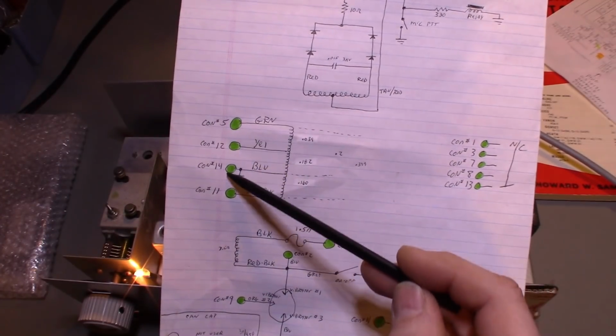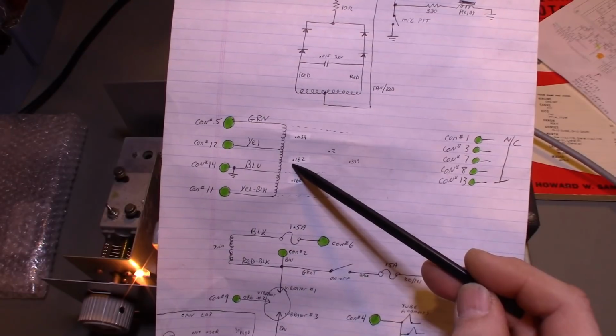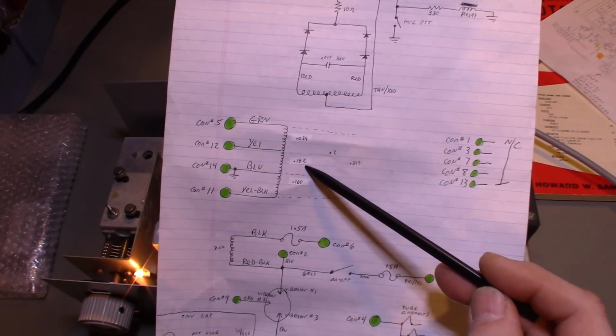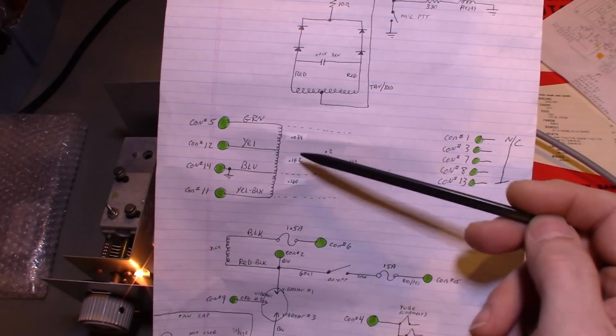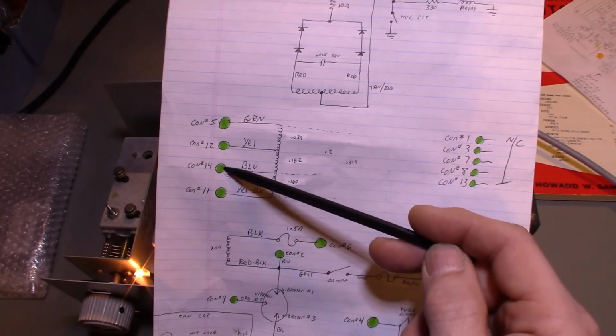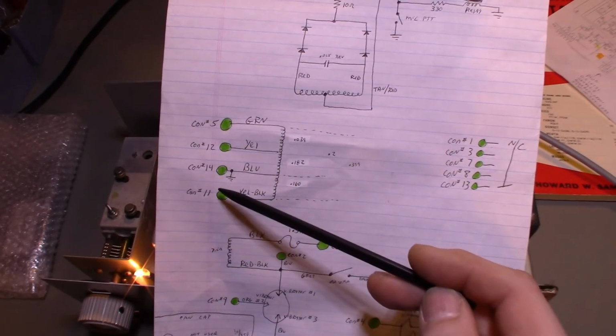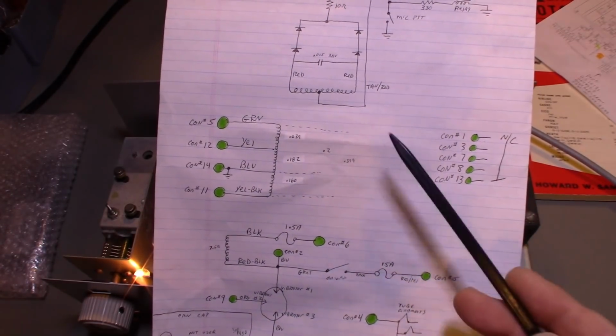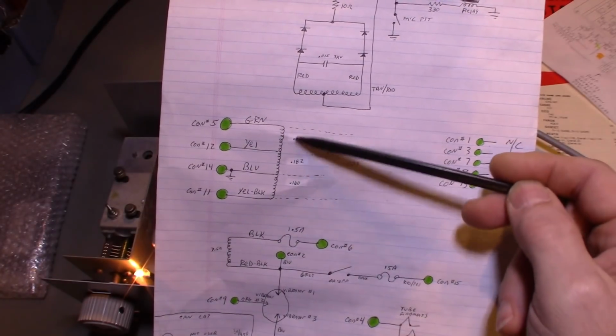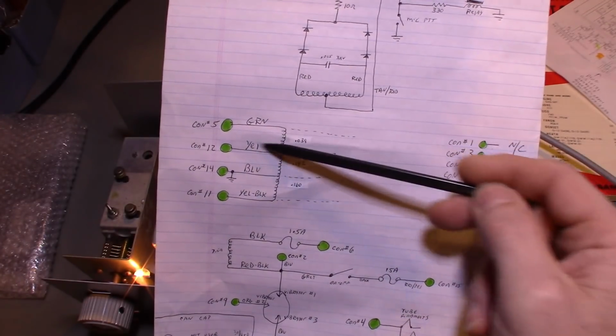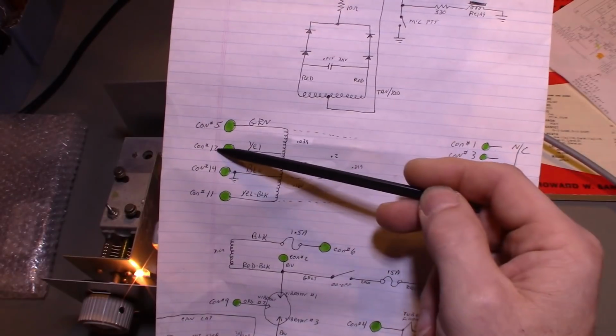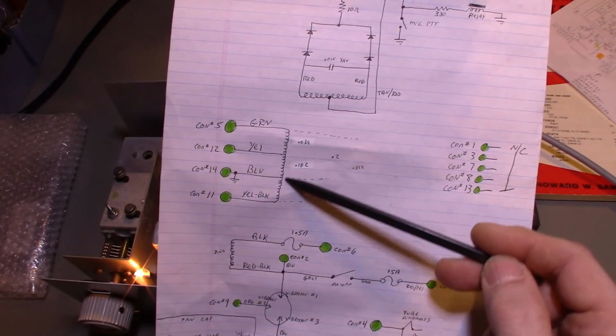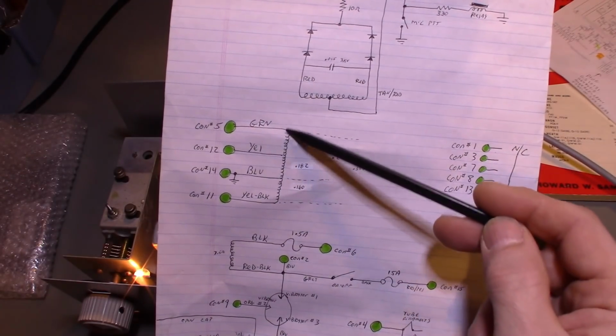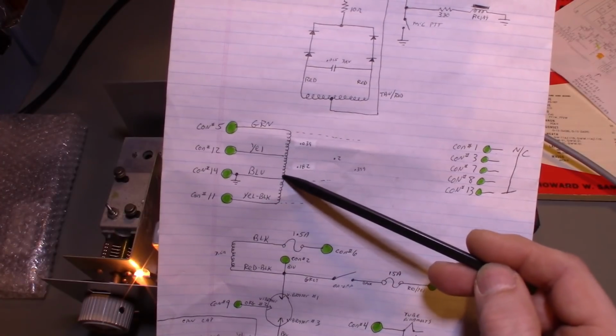Between contact 5 and 14 I had 0.182 ohms. Then I'd be measuring between this terminal and that one and so on, just going back and forth in a process of elimination. You can figure out the lowest resistance pair are windings that come in and go straight out, and if you find more resistance in circuit, that means it had to go through more windings in the transformer.